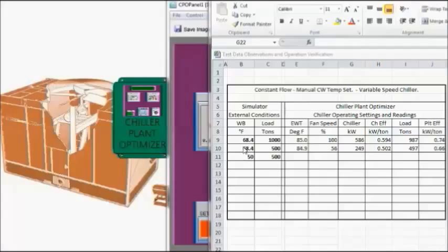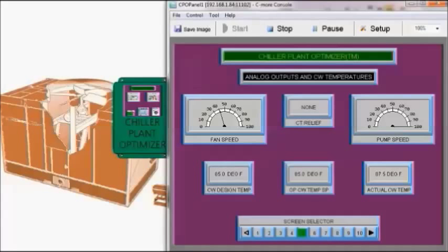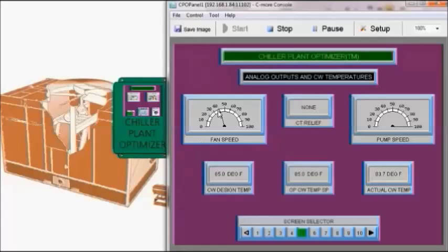Here's our data record when we dropped it to 500 tons. Now I'm going to make another change and this is just to drop the wet bulb temperature to 50 degrees Fahrenheit. The big change here is the reduction in fan speed again just due to the lower wet bulb temperature and the cooling tower doesn't have to work as hard.